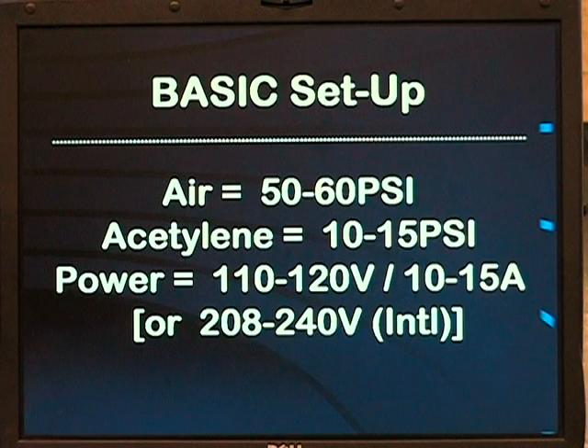These are the basic setup services required for proper operation of your Model 205 AA. A source of clean air between 50 and 60 psi is required for a proper air-acetylene flame. Acetylene should be set no less than 10 psi and ideally at 15 psi to get the most stable flame. As previously noted, the electrical requirements are 110, 120 volts, 10 to 15 amp for most US service, or 208 to 240 volt for international or industrial service.